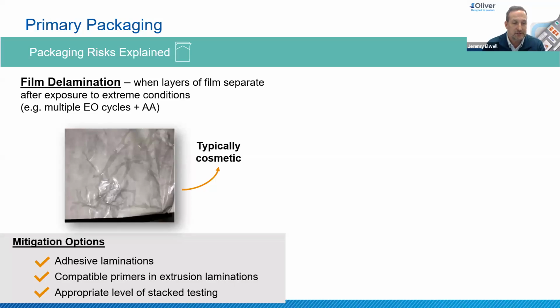So some mitigation options. We talked about these being extrusion laminations, which I'll have a photo of later with a study that we have. A mitigation option is to use an adhesive laminated film, and that's much stronger. It could withstand these extreme environments, but also gas sterilization like chlorine dioxide. And also, looking further into extrusion laminations, there are primers that are compatible with extrusion, so you can consider those for your testing and appropriate levels of stack testing as well. There's a lot of guidance out there, and a lot of standards we have to follow in the packaging world. Really understanding what testing is necessary and trying to avoid unnecessary stacking of those tests.